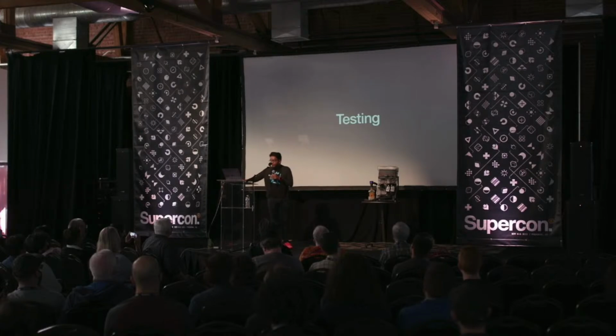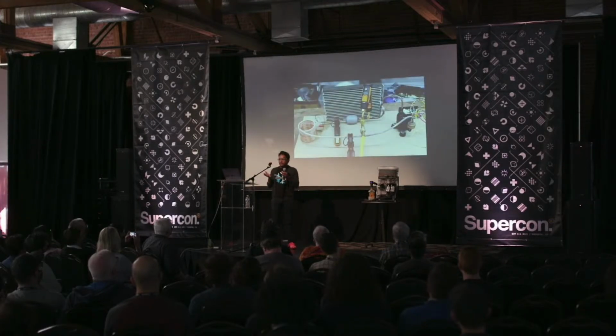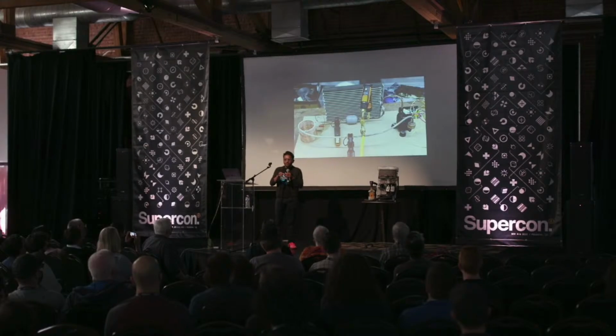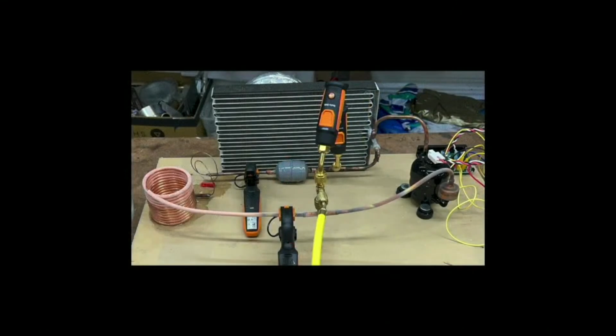The next step after that is just pulling a vacuum and starting to charge the system. You start charging from the low pressure side, and it's traditional to use Schrader valves, the same kind of valves used in bicycle tires, and the automotive connectors for those are relatively inexpensive. Here, the yellow tube is connected to a can of propane, which is the refrigerant used.